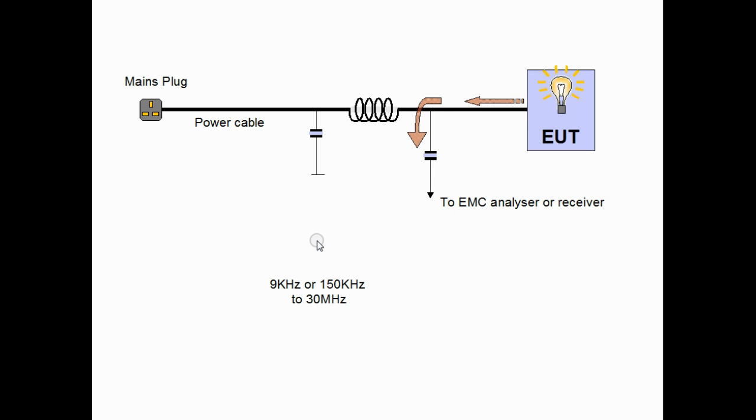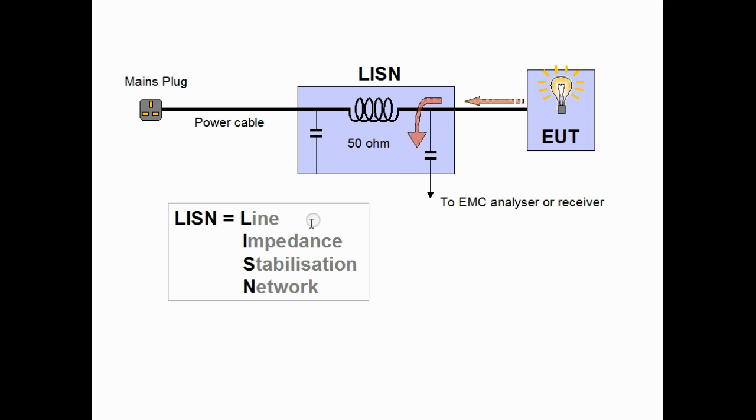What we do is to add in a network which means that the impedance as seen from the EUT is consistently 50 Ohms. So if we all use the same network, we'll all make the same consistent readings. The network is specified by the standards and we should all use these networks. The network is called a line impedance stabilization network because it does stabilize the impedance of the line.